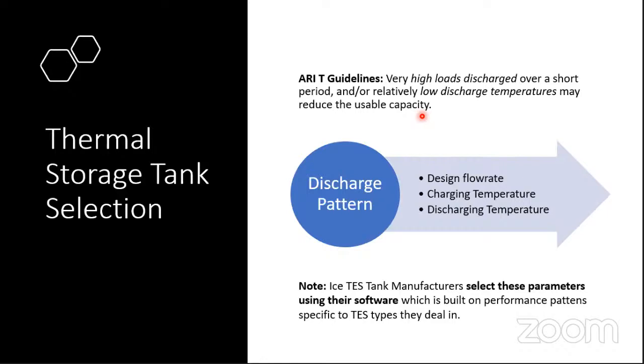That is one option. The other option is that I might wait a little longer for that entire ice cube to melt and get my cooling. So here I'm trying to explain an analogy between waiting more time and more number of ice cubes. More number of ice cubes means a high load discharge, and waiting more time means low discharge temperatures. I'm giving more time. So my ice melting is going to be temperature dependent and flow dependent. So as a thermal storage tank designer, as an ice storage tank designer, I should start thinking about these things.